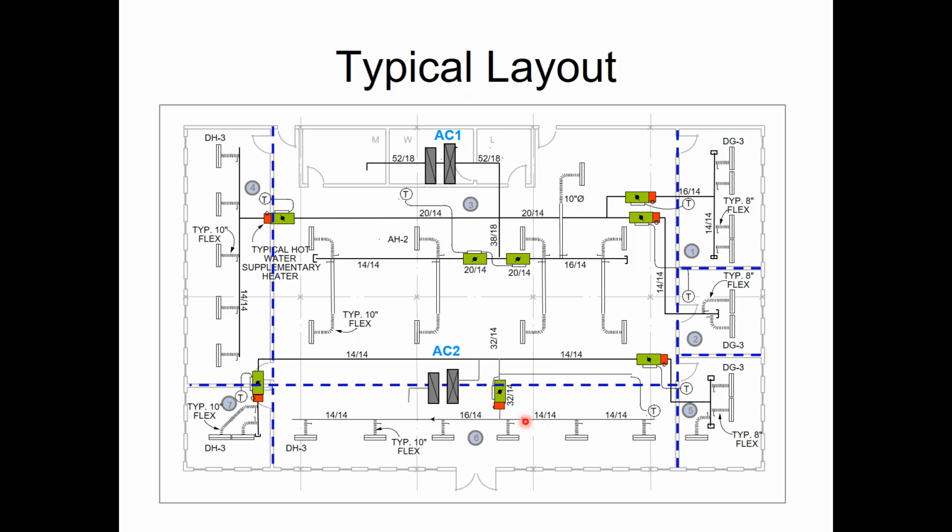So in this case, we have 1 that is serving the south zones, so the main south zone plus the 2 corners. And then we have another system that is serving the interior core, the east, and the west. I'm not super excited about this at all. I would never have signed off on this, but this is what happens in real life.